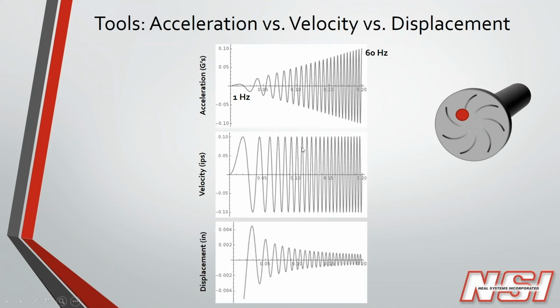And then I'm going to show displacement here just to point something out, and that is when we get into really high-speed machines, it's pretty typical to see fluid film bearings. And in the case of a fluid film bearing, the shaft isn't ever in direct, metal-to-metal contact with roller elements in a bearing, for instance. And so the vibration is a lot harder to measure if you're trying to look at the shaft motion. So what we tend to use is a displacement proximity probe. And the interesting thing here is as the machine gets faster and faster, that displacement probe, based on this curve, is actually getting less and less sensitive for us. So there's a bit of a challenge there, but it's just interesting to point out that the sensitivity could be a concern for displacement at higher frequencies.